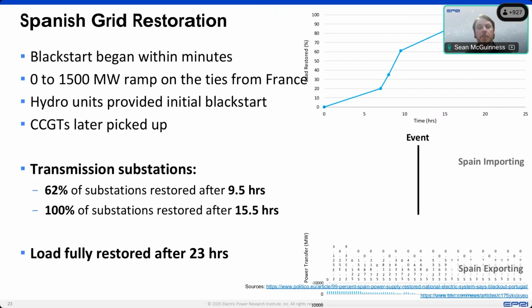It took about 9.5 hours to get 62% of the substations re-energized, and all of the substations were restored after about 15.5 hours. So in the context of an approximately 40 gigawatt grid at peak, this is how long it took them to restore everything. We don't have exact data points for their exact sequence, but from those that are made available, we have this chart in the top right that shows we go from 0 megawatts up to 100% after just under 24 hours, when 100% of the load was connected.